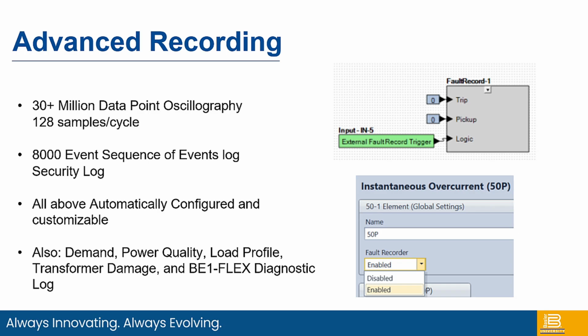Another function that the Flex has natively is advanced recording. So it's got a very strong and huge processor in it for a protective relay, with a 30 million point data array, and you can trigger it with a huge portion of functions. So by default, the protective functions are going to have the fault recorder turned on. You can turn it off, for example, if you are just having a control function or something that you don't want to use up your oscillography capture information for.